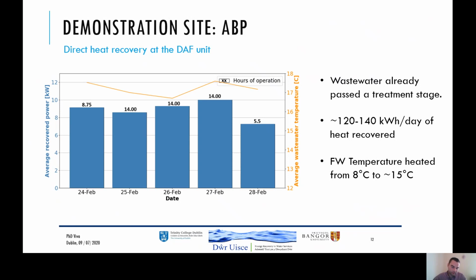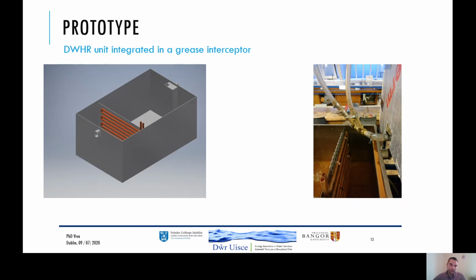This preheated the incoming fresh water from 8 to 15 degrees Celsius. Lastly, we then looked at integrating a heat exchanger or a heat recovery device into a grease interceptor. These grease interceptors are already mandatory pieces of equipment in commercial kitchens, and our idea was to reduce space constraints and reduce capital investment in this heat recovery device by combining these 2 systems.